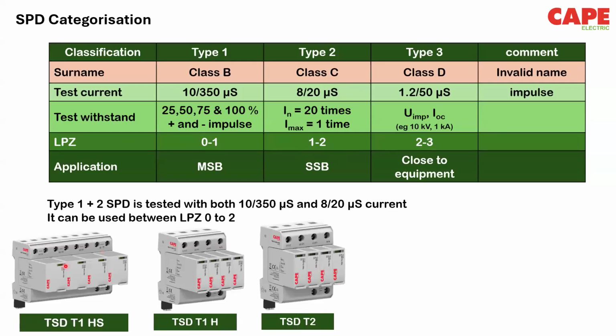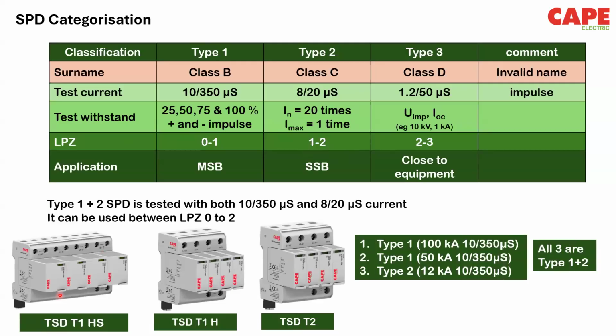So what are these SPDs? This is how generally an SPD looks like, and all type 1 SPDs are type 1 plus 2. That means they are tested for both type 1 and type 2 application. So you can use it in both these applications. But if you see here, this type 1 is tested for a 10 by 350 100 kA lightning impulse. And this type 1 is tested for a 50 kA lightning impulse. And this type 2 is also tested for a 10 by 350 lightning impulse. But its surge current is only 12 kA. So even type 2 SPDs can become type 1, but it cannot withstand a higher surge current. That is why we don't use type 2 SPDs for a type 1 application.